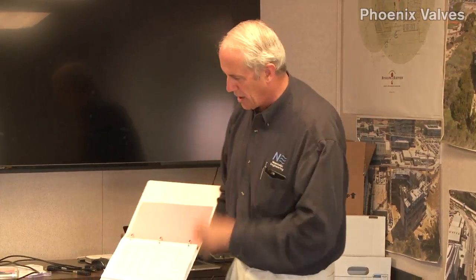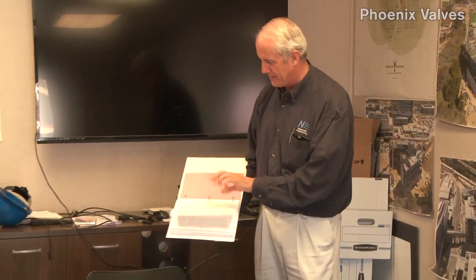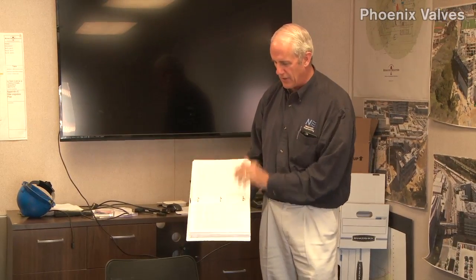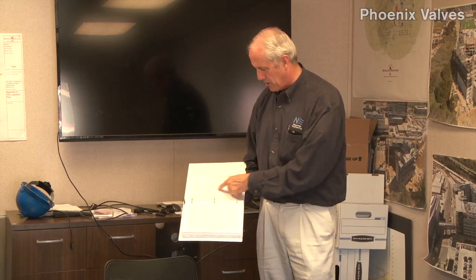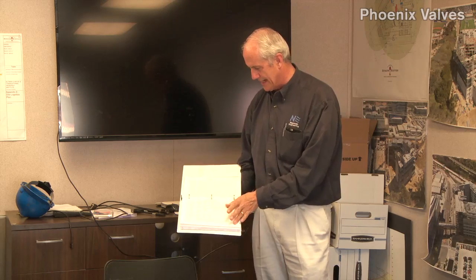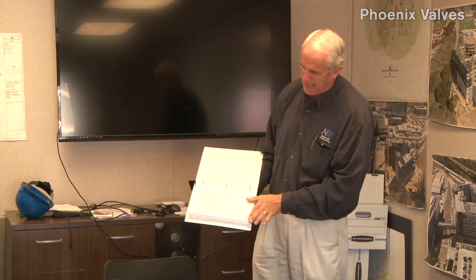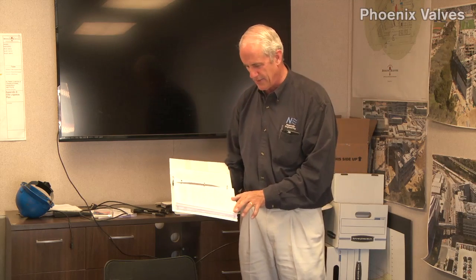At the beginning is what we call a room schedule sheet that lists, in order of room number, every valve we have on the job. How much airflow it's doing at min and max, what the size of the valve is, what the function is of the supply, exhaust, fume hood, whatever. So we have 7 pages or 8 pages of valves, fume hood monitors, and other things in here.